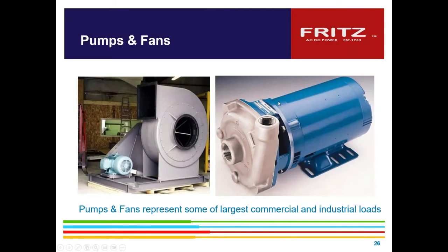And then there's various types of pumps that are operational, that run at variable speed, that also can. The issue on pumps, you have to be very careful, though, is that you watch where is the sweet spot of that pump and that impeller to produce power, so you don't get off the pump curve.